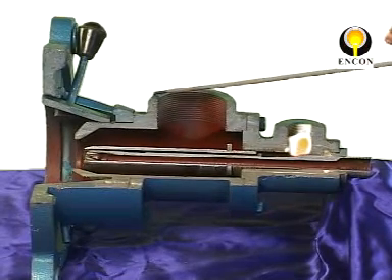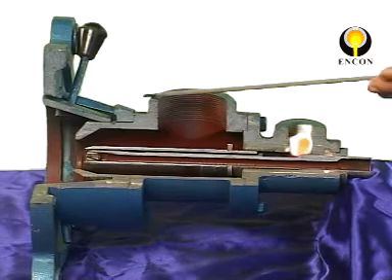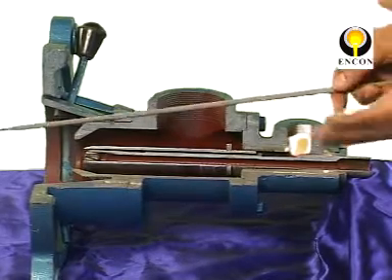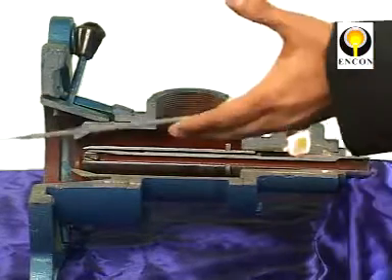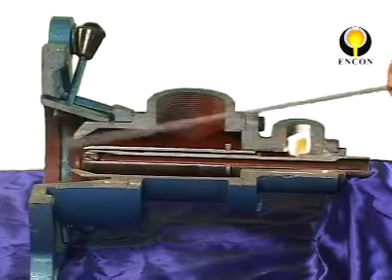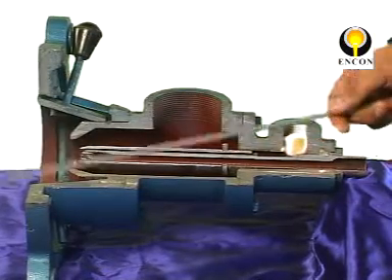In this burner, we require five to ten percent excess air levels, whereas in conventional burners, it was up to 25 to 40 percent. This excess air did nothing but just went inside and cooled the furnace.